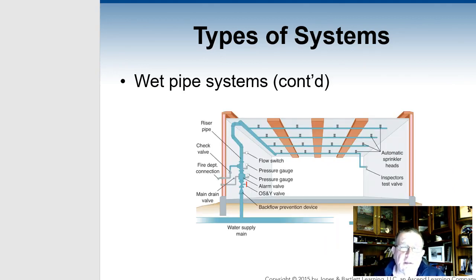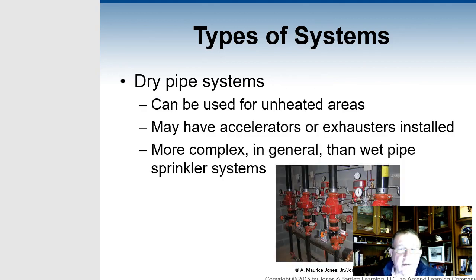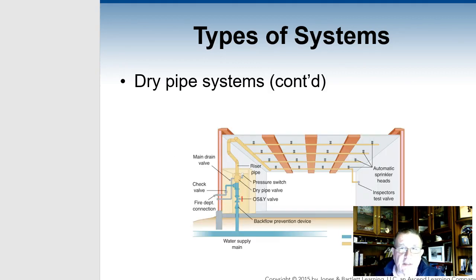But the big thing is look at a water system, a sprinkler system that's wet. It's a grid system. Water comes up, water goes through the grid, and it sits there and waits to be activated. And once it's activated, the head pops off, water comes out. The big thing is there's other types of systems. The dry system, where there's systems under pressure, where water is held behind by a baffle, and at the same time when the head pops off and all the air releases out, the baffle opens up and water comes through the system and the whole system becomes wet. That is some of the stuff that you probably see every day. The systems are very similar.